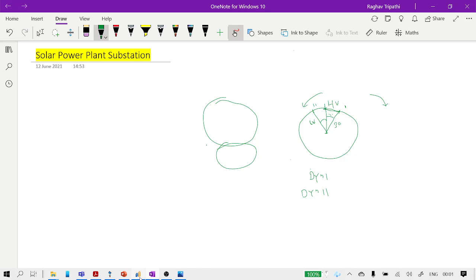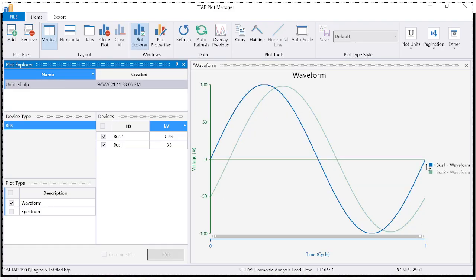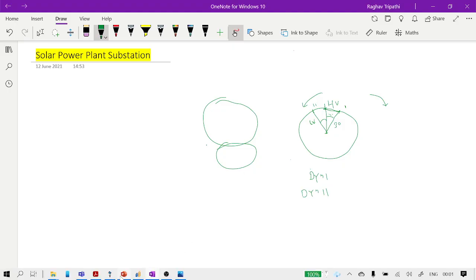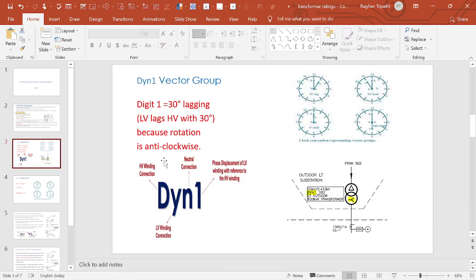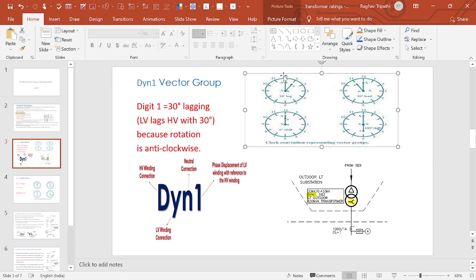We can also see this on a graph or in ETAP. The blue line is HV and the LV is leading by 30 degrees — that is the meaning of DY11. In DY1, HV winding is delta, LV winding is star with neutral, and 1 means LV is lagging 30 degrees from HV because rotation is anti-clockwise. At position 12 there is zero phase shift, at position 6 there is 180 degree phase shift.